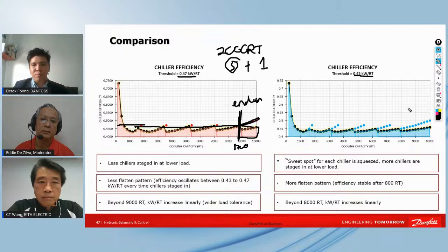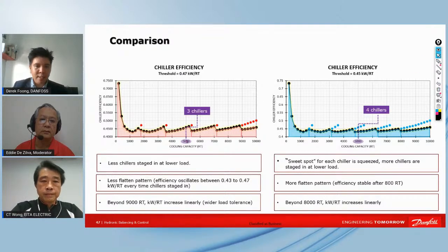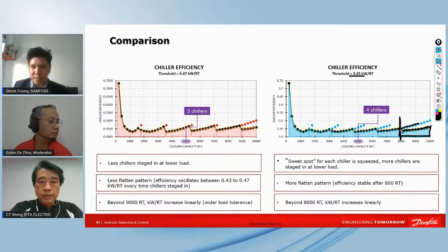So of course, this is also where we can see at what load condition you have more chillers or fewer chillers. The fewer, the better the efficiency you want, then this part here will be slightly compromised on the capacity, unless you want to use the standby unit to maintain the efficiency. But of course, this can be seen in the system when it's running its analytics. And that's one. It's not so holistic yet. This is just the chillers.